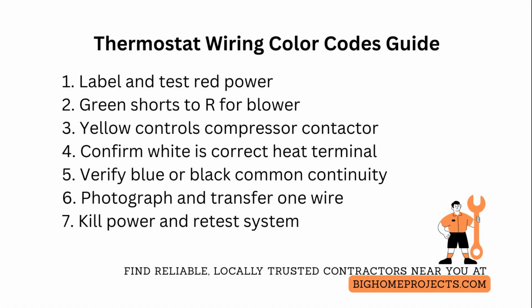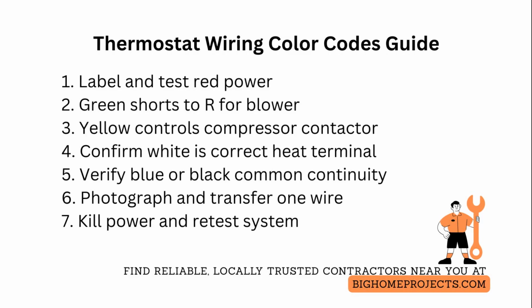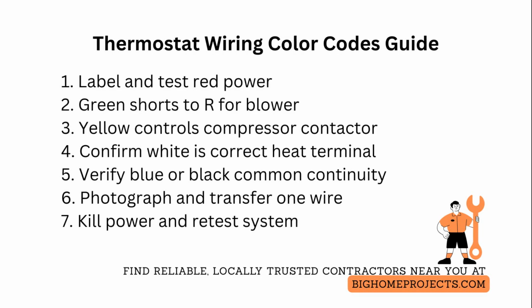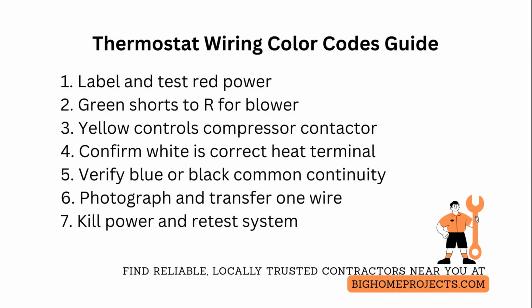Blue or black is commonly used as the common leg, labeled C, and it completes the 24-volt circuit so modern smart thermostats can draw power. Verify continuity to the transformer's C terminal and avoid using a ground as a substitute.